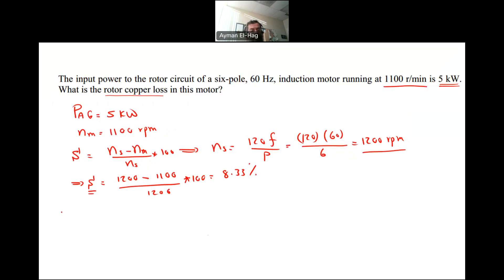Now, once I know the slip, I can find the P convert, which is nothing but 1 minus the slip times PAG, which is equal to 1 minus 0.0833 times the 5 kilowatt. And this will give me a power of 4.584 kilowatt.